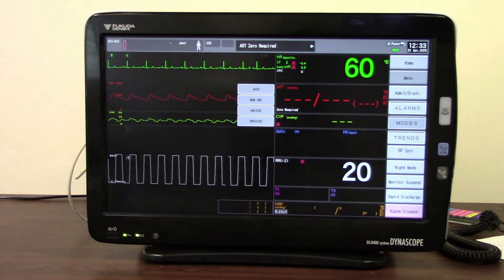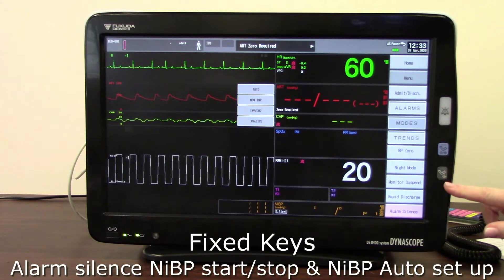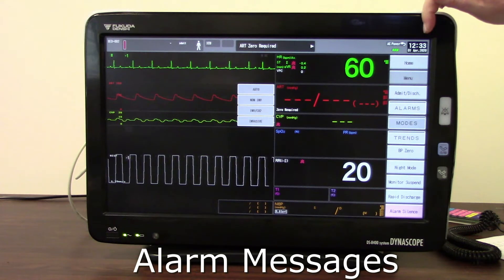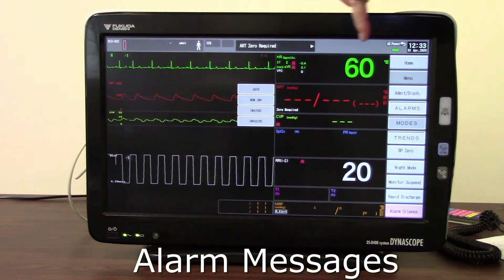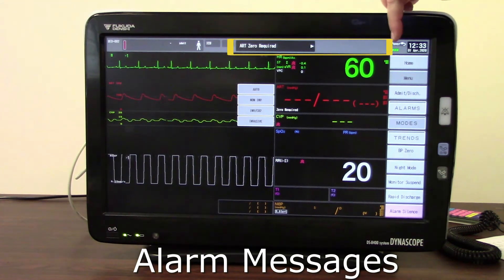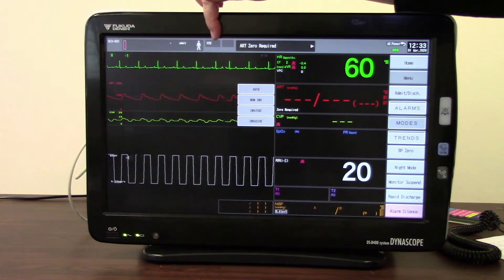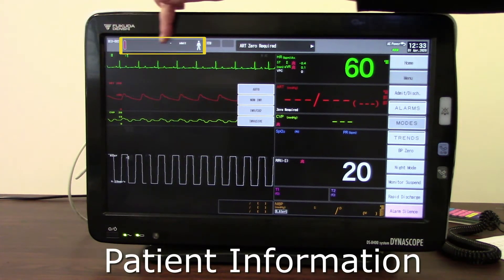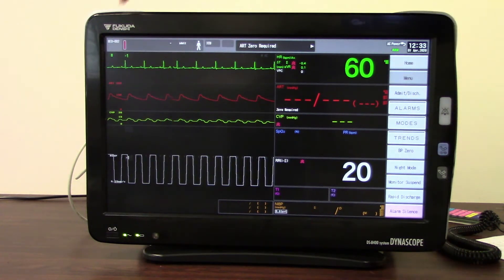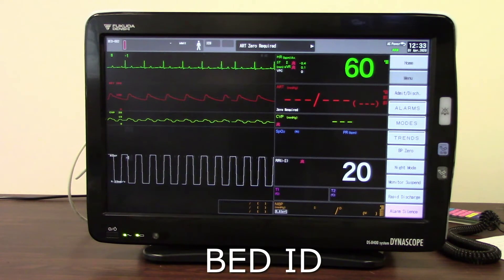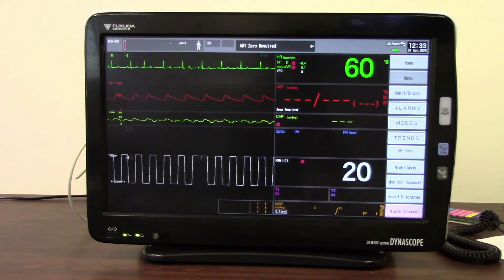User keys you may see along the bottom or you may see down the left hand side. There are also three fixed keys here on the right hand side. Time and date here on the top right hand corner — this is where you'll see any alarm messages that may occur. Your display will be here and also this is your patient information area, and in the very top left corner you'll see either your bed number or your channel number.